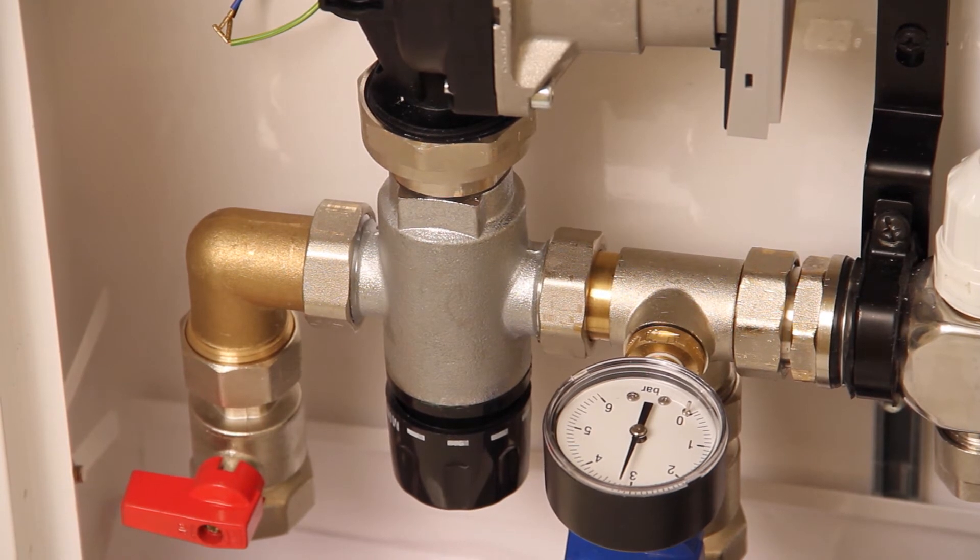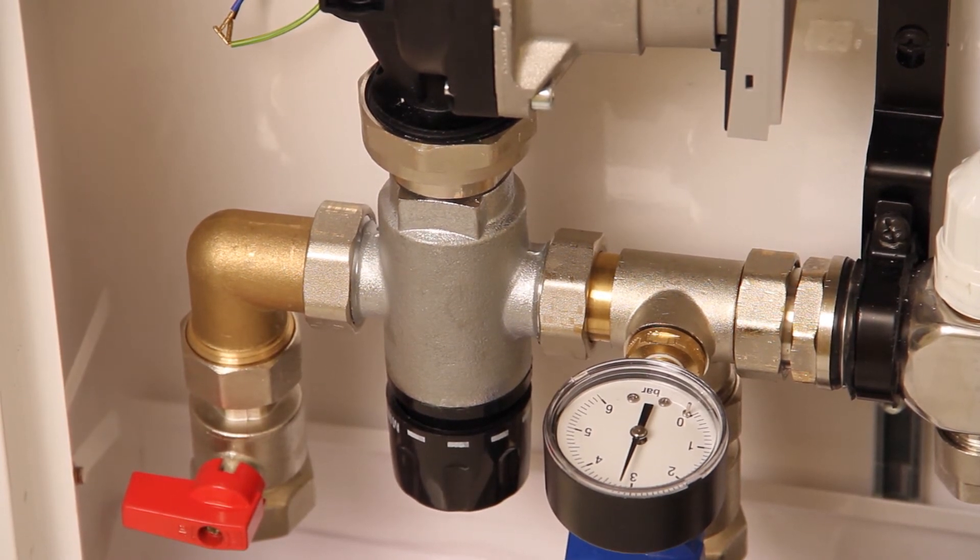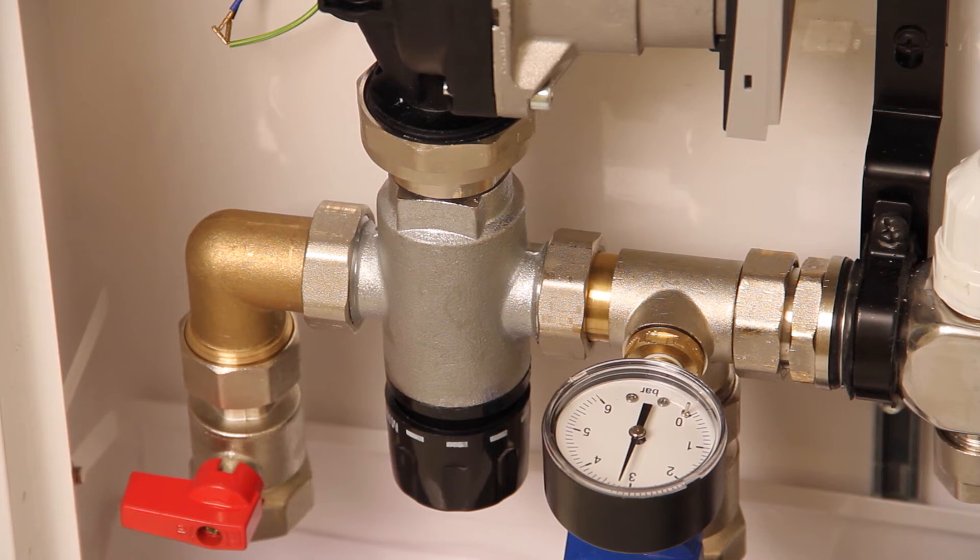Allow the system to remain under pressure for at least three hours. If the pressure drops, investigate and remedy the loss of pressure.